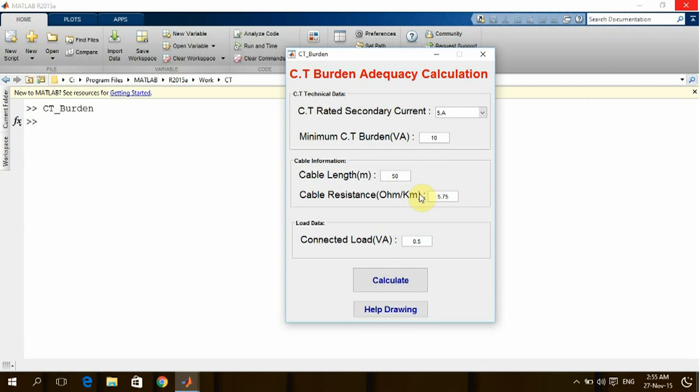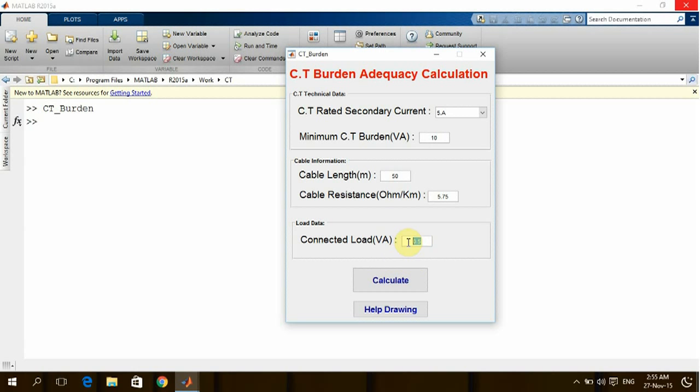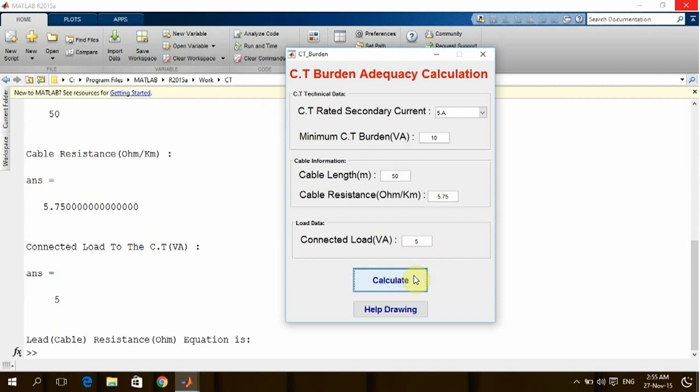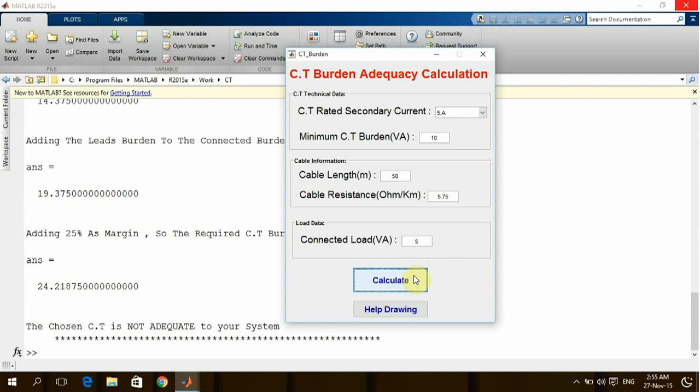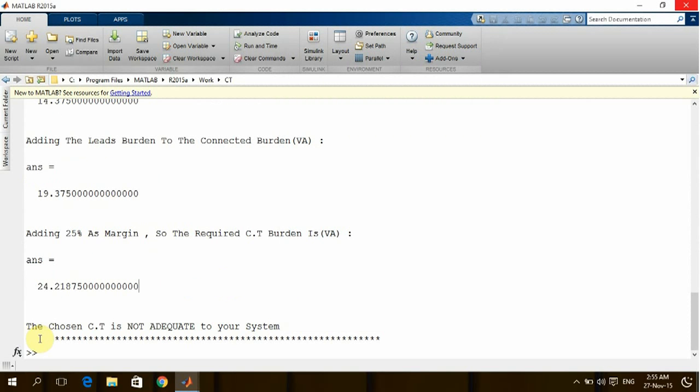Here the connected load—the overall load from the whole relays connected to this CT—let's consider the volt ampere is five from all relays. Right now let's calculate. The program is giving me that the chosen CT is not adequate to your system.